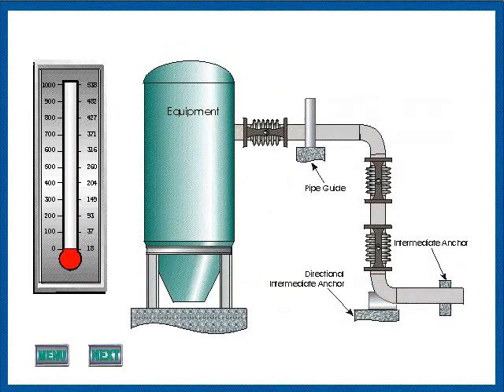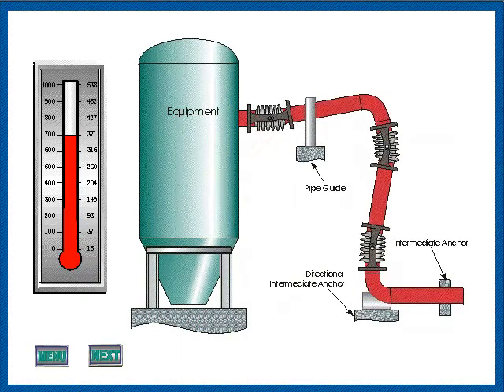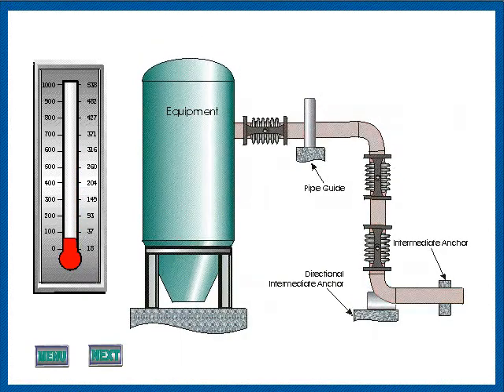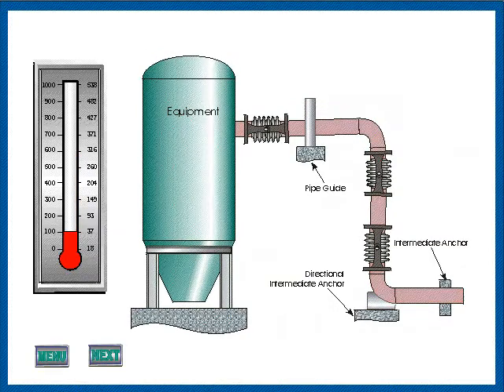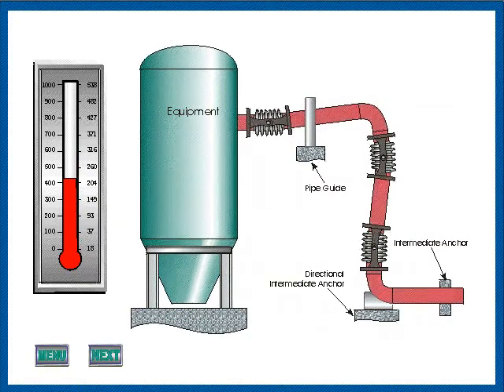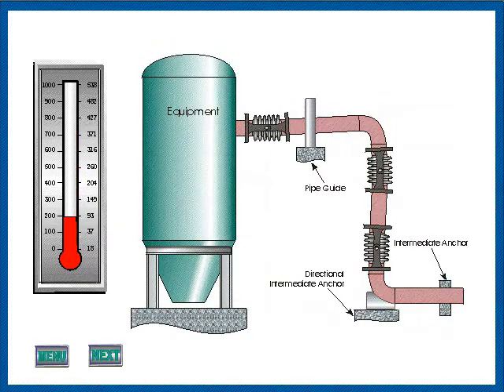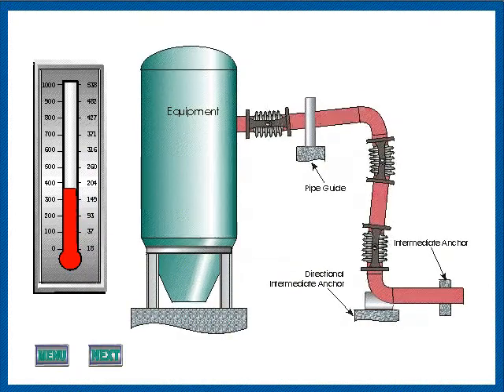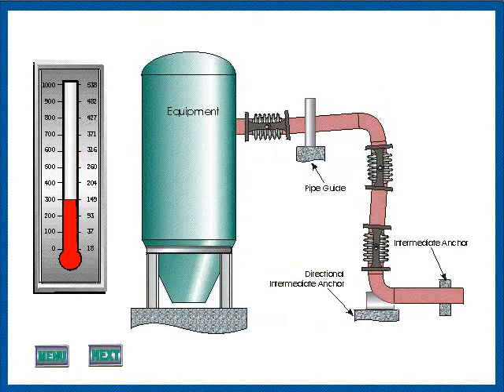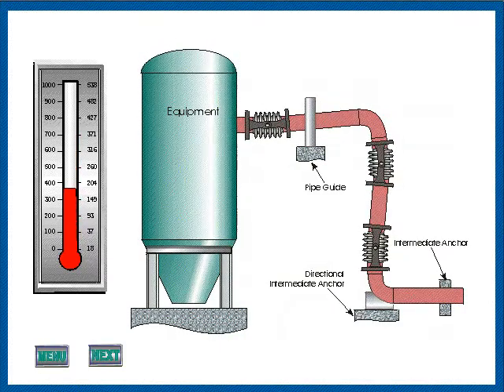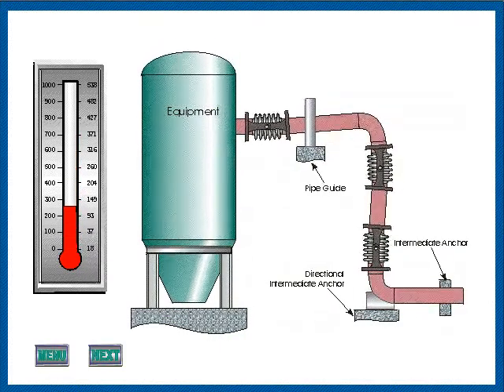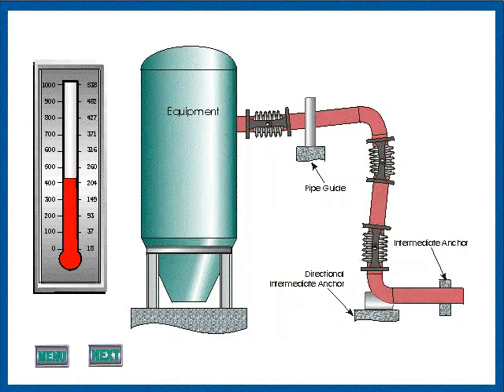A hinged expansion joint system may be used effectively in applications involving movement other than the pure thermal growth of piping. This animation illustrates an application combining the thermal expansion of a piping system with the single plane movements of a piece of connected equipment. So long as all movements are restricted to a single plane, the behavior of the expansion joint system is quite similar to that of the system shown in the dual or universal lateral expansion joint animation.